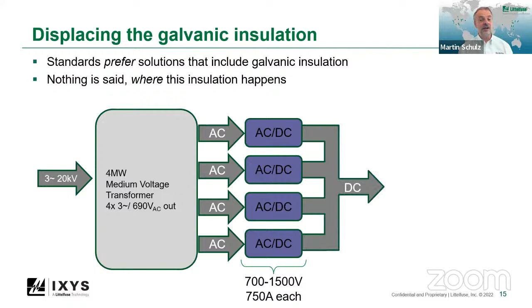The transformer efficiency of a medium voltage transformer is unprecedented. They all run 99 point something percent, even 99.9 has been proven. And the insulation in the transformer is meant to support 100 kilovolts. So yes, the battery is separated from the grid with galvanic insulation. Standard, fulfilled. It reduces material consumption because now the AC to DC converters no longer feature insulation on their own, which in turn increases the power density of the power electronic section. It would also allow for redundant operation if properly connected.